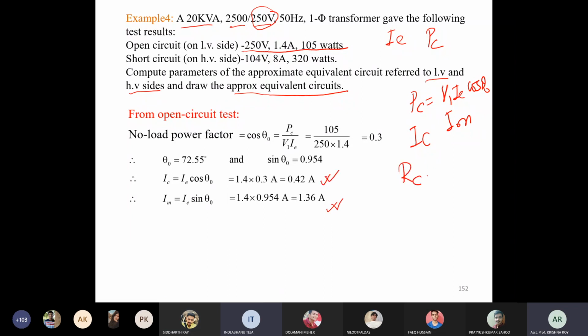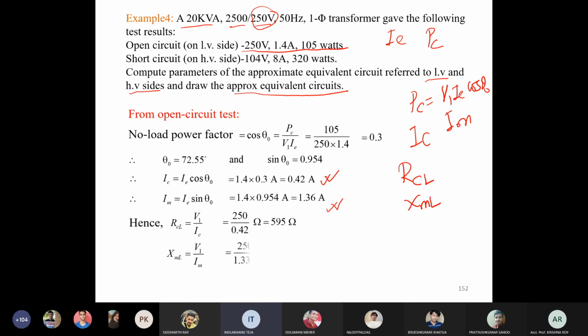Now calculate RC, refer to LV side, so RCL, and calculate XM, refer to LV side, so XML. RCL is V1 by IC, XML is V1 by IM. So RCL, how much is this? 595.2 ohm. 595 ohm, and XML 187 ohm. Correct? Yes. So these are the low voltage side parameters or shunt branch parameters we have determined from the open circuit test. Now consider the short circuit test.